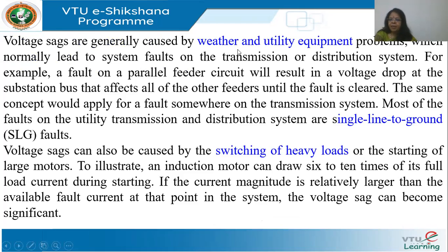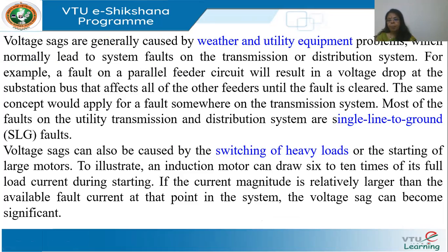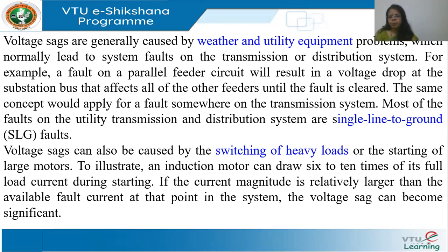Sags are typically caused by weather leading to system faults — very hot weather can cause lines to sag, touch a tree, and cause a short circuit or single line-to-ground fault, which causes a voltage sag in one phase. Switching on a heavy motor also causes a voltage sag because the motor draws a huge starting current — process industries use motors up to 5000–10,000 HP that can draw 10 times normal current.